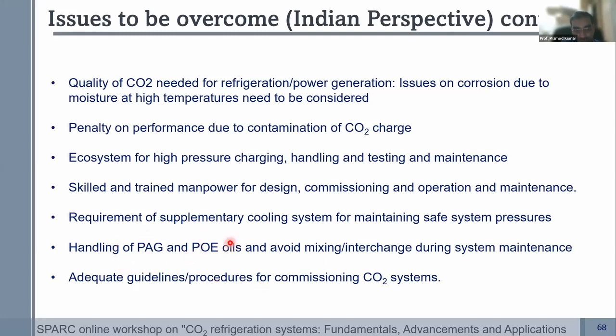These oils can also be harmful to the environment. So the discharge of these oils, polyolester oil and PAG oils, has to be done correctly. And you should avoid intermixing during system maintenance. You have to drain it out and refill it. So these are issues that can certainly be addressed, but they are a hindrance to the development of these SCO2 systems, particularly when you're building it for the first time.